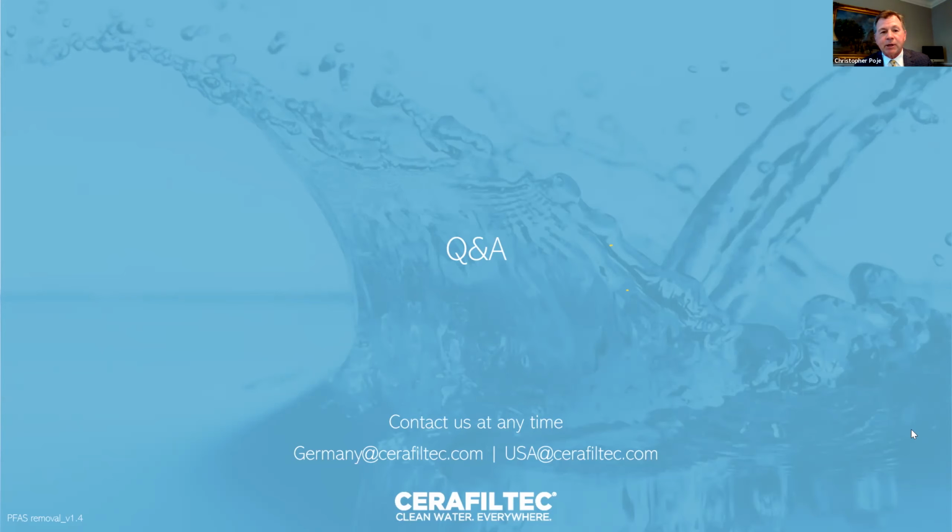Yeah, and it's key. If you look at our membranes, one of the competitive differentiators is almost perfect hydraulic performance, in that each plate and each square inch or square meter of the plate gets uniform hydraulic flow throughout. So we're not getting hot spots or shortcuts. And when properly calculated, the amount of carbon that we add to the tank is almost 100% used and, if you will, stuck to the outside of the ceramic plates during the filtration cycle. Perfect. That's how the cake's built. Perfect. How often do you remove the cake layer? I think this was already discussed.